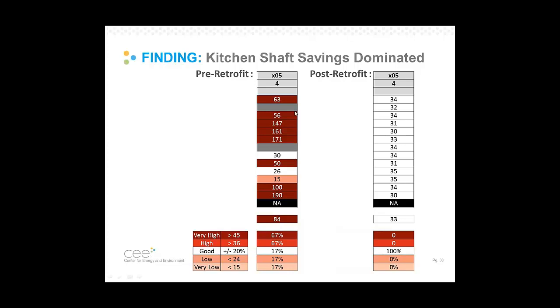Here's a look at what happened before and after the retrofit on a kitchen shaft. This building had, I think, 10 or 12 shafts. Some were serving kitchen inlets and some were serving bathroom inlets. This one shows top to bottom inlet flow measurements on each floor of the kitchen airflow. You can see that there are high airflows, which are dark reds, and the pinks are the low airflows, below the recommended amount. When we're within the tolerable recommended amount, it's white.